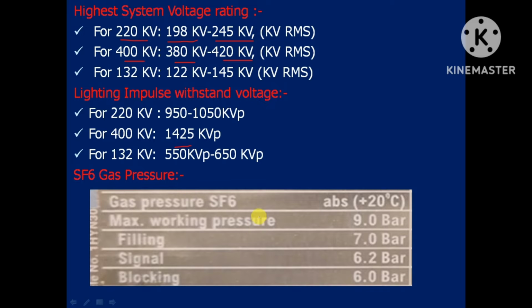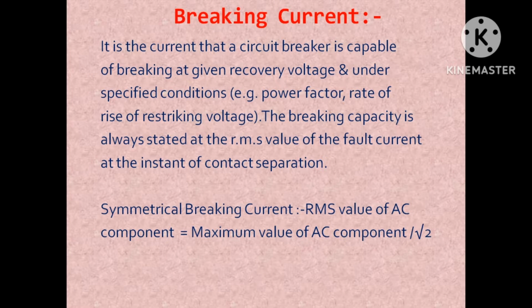And as mentioned in the nameplate details, for SF6 gas pressures, the maximum working pressure will be 9 bar, filling pressure will be 7 bar, signaling pressure is 6.2 bar, and blocking pressure will be 6 bar. Signaling pressure means the alarming pressure. Blocking pressure means the breaker will be locked out, so the breaker cannot do a breaker operation during the time of lockout. One is called the breaking current, one is called the making current. Both are important from the design point of view of circuit breaker contacts and the material going to be used.